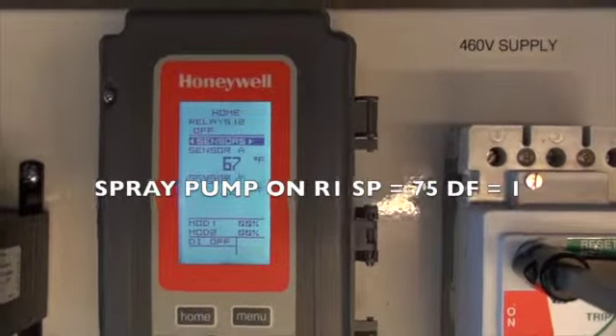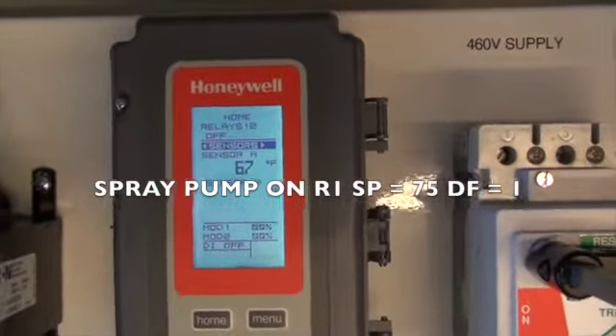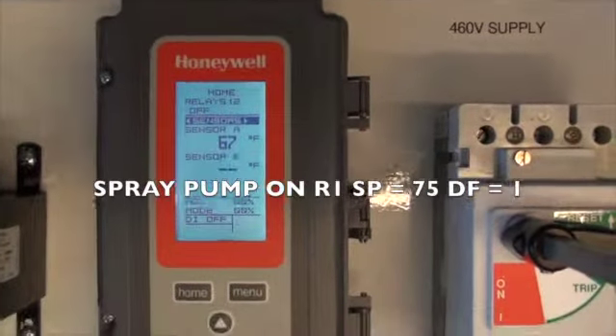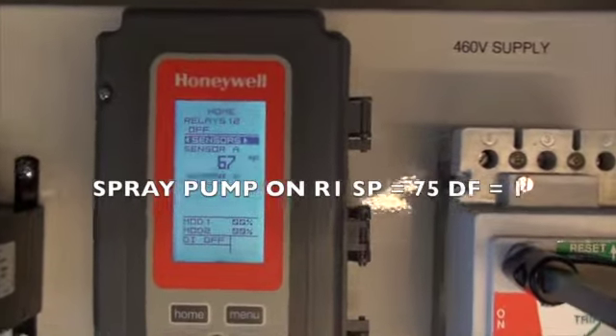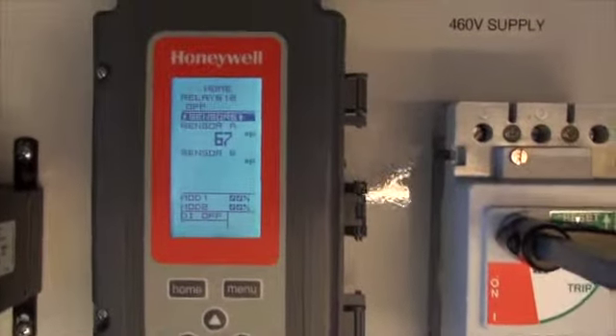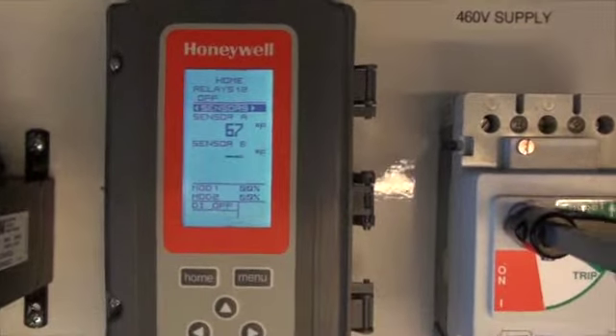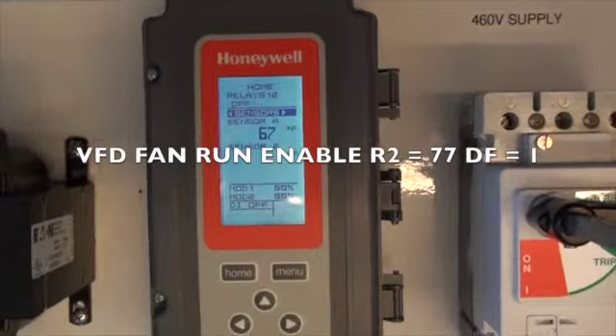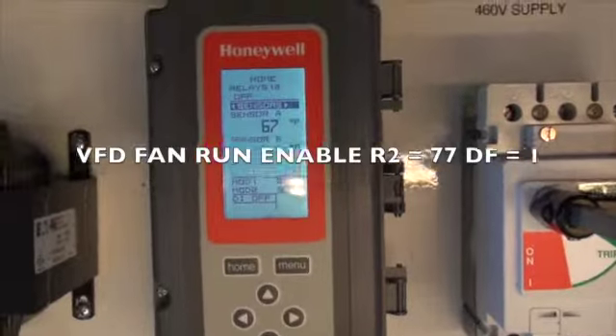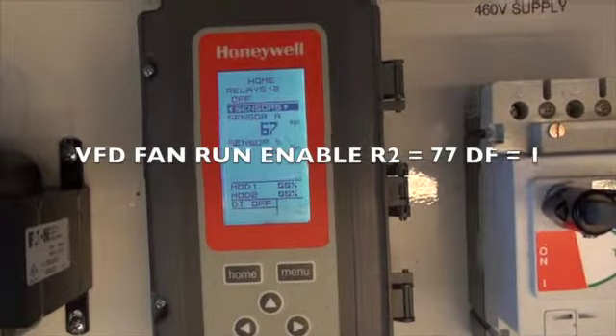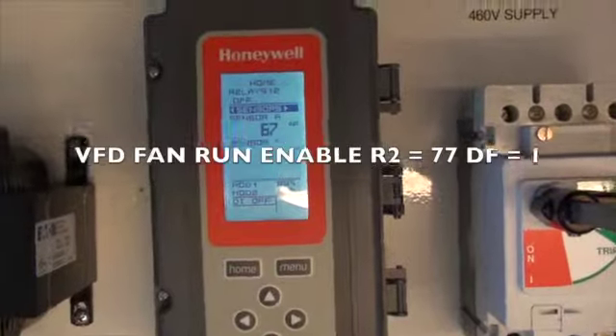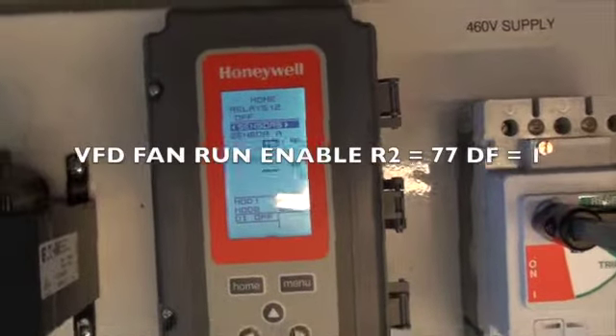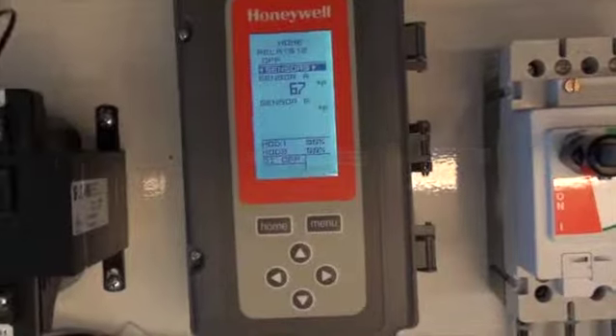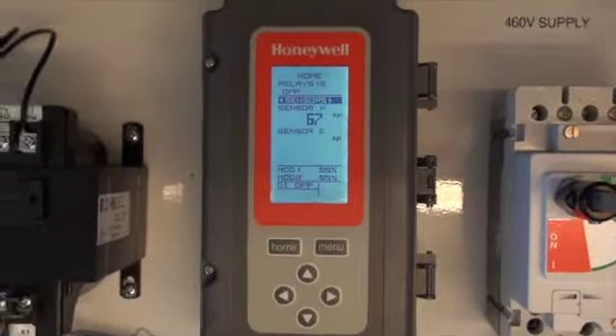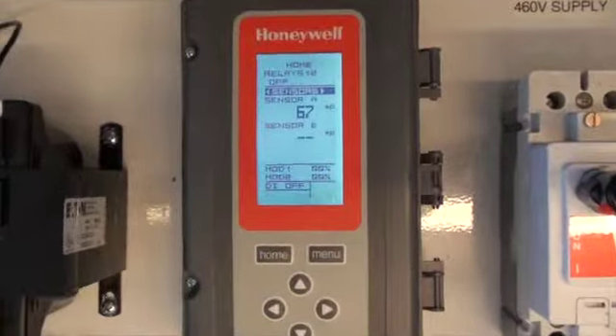Then your spray pump, you want to make sure that the spray pump always starts before the drive or the fan motor enables. So you set your spray pump or relay 1 output to say about 75 degrees and always keep a differential between 1 and 2 degrees on the spray pump. And then set your relay 2, which is the drive enable, which is where the drive actually enables it to run forward. Set that a couple of degrees higher than the spray pump so that your spray pump comes on first. You get a little cooling from the spray pump. But most importantly, and especially in open towers, you want that spray pump to come on first, so you got a good flow of water over the tower before the drive, the fan motor comes on and starts ramping up. This is going to be your most efficient way of setting up this controller.